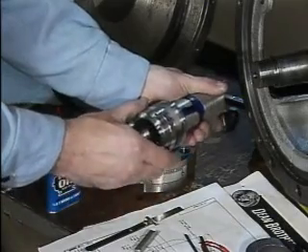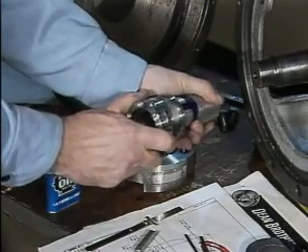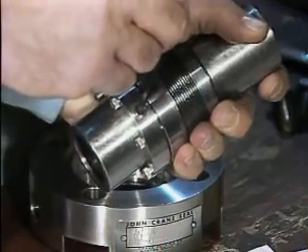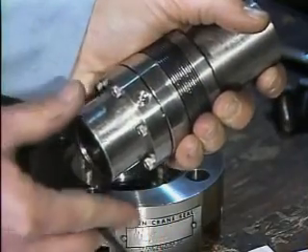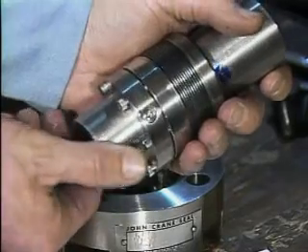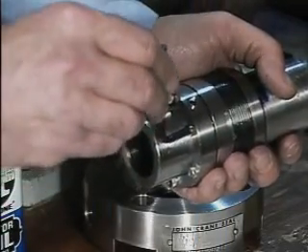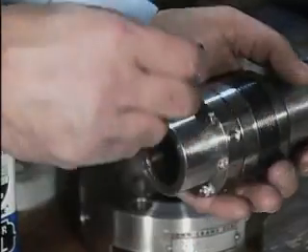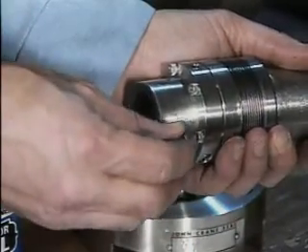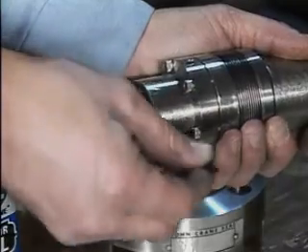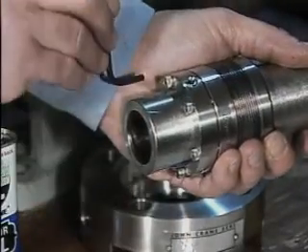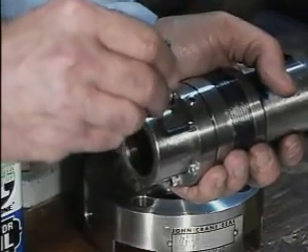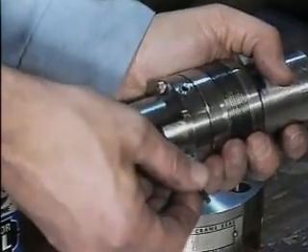After the sleeve has been marked for the location dimension, the rotating element is placed into its proper position. Then the set screws are partially tightened to hold the collar in place. Since this collar uses a gasket to seal around the shaft sleeve, the cap screws on the collar are tightened to compress the gasket. These screws should be tightened in a crosswise pattern so that the pressure against the gasket is even.